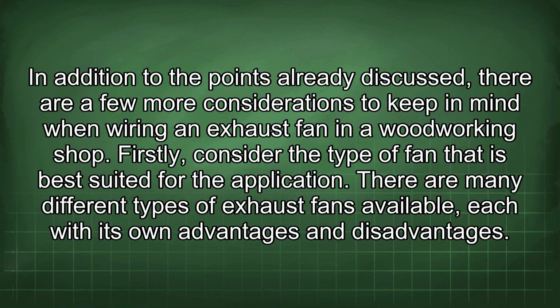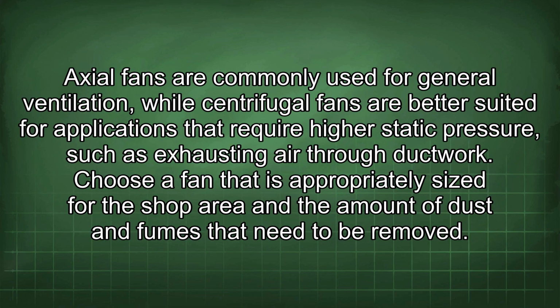In addition to the points already discussed, there are a few more considerations to keep in mind when wiring an exhaust fan in a woodworking shop. Firstly, consider the type of fan that is best suited for the application. There are many different types of exhaust fans available, each with its own advantages and disadvantages. Axial fans are commonly used for general ventilation, while centrifugal fans are better suited for applications that require higher static pressure, such as exhausting air through ductwork. Choose a fan that is appropriately sized for the shop area and the amount of dust and fumes that need to be removed.